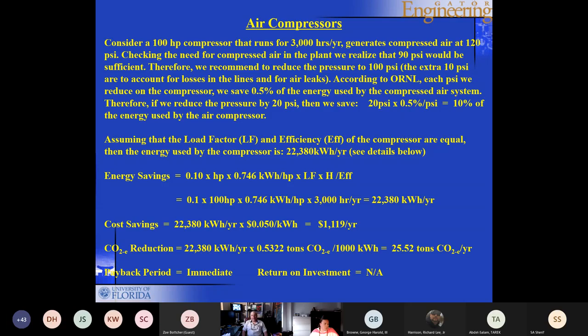So we identify the need, and then we say, all right, you guys need 90 psi, but we're going to give you 100 psi to allow for losses in the lines and for any possible air leaks. So now they're no longer running the compressor to produce 120 psi compressed air, but 100 psi compressed air. And if you look up what Oak Ridge National Lab recommends, they say for every psi that you reduce in the pressure in the line, you save 0.5% of the energy used by the compressed air system. So in this case, now we have saved them 20 psi. So we take the 20 psi, multiplied by 0.5%, and we end up with 10% of the energy used by the compressor as savings.